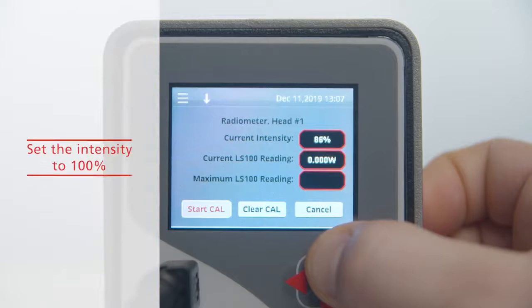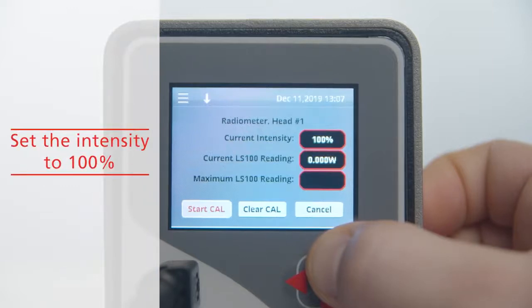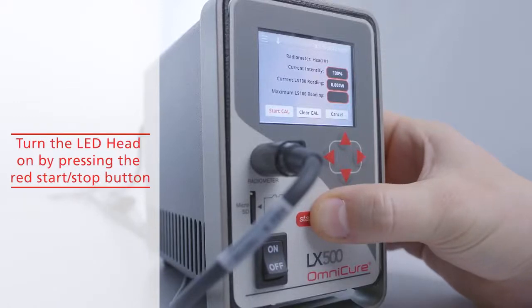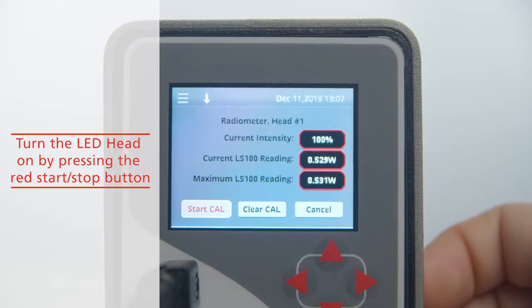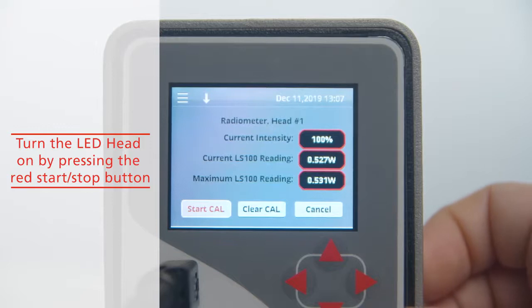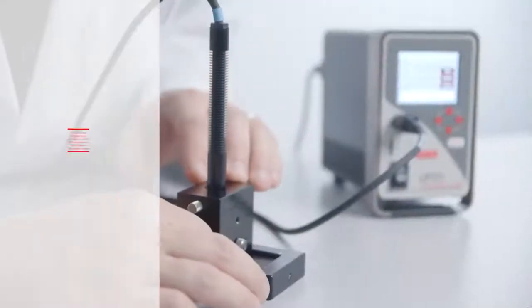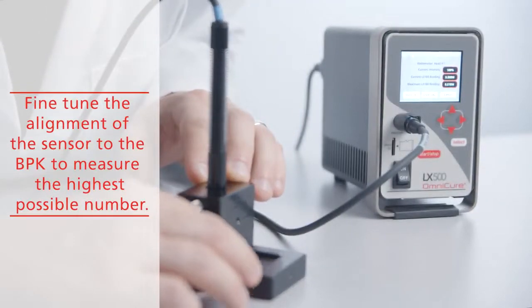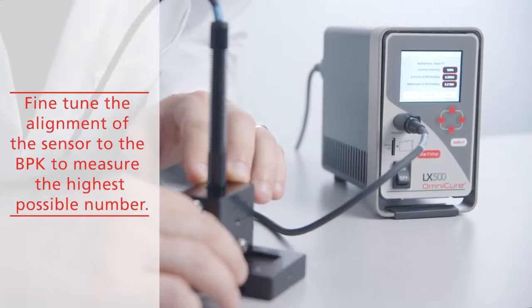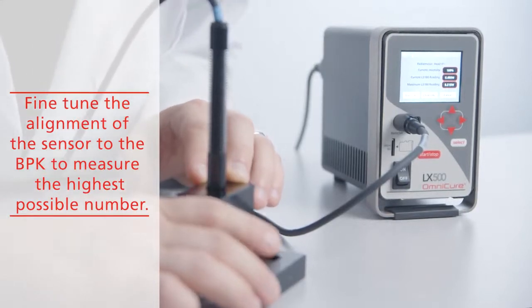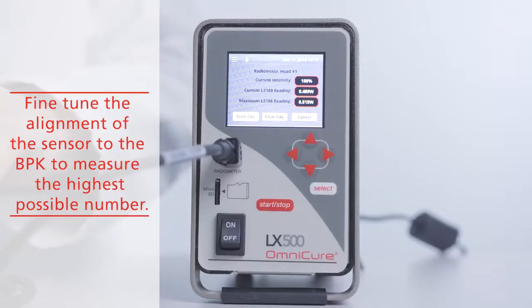Set the intensity to 100% before beginning the calibration by using the up arrow key. Turn the LED head on by pressing the red Start/Stop button. The head can be confirmed turned on once the values start appearing on the screen. Fine-tune the alignment of the sensor to the beam positioning kit by turning the X and Y thumb screws on the beam positioning kit base to measure the highest possible value. The maximum LS100 reading area will show the maximum achieved reading.